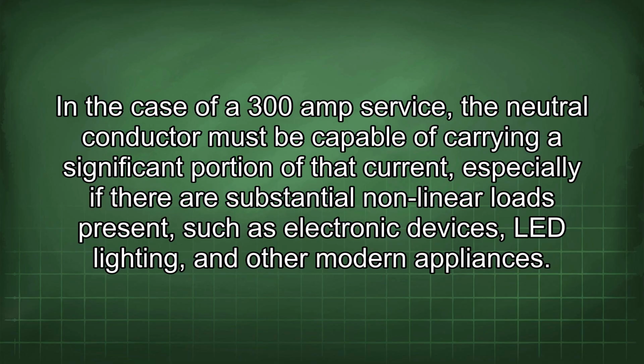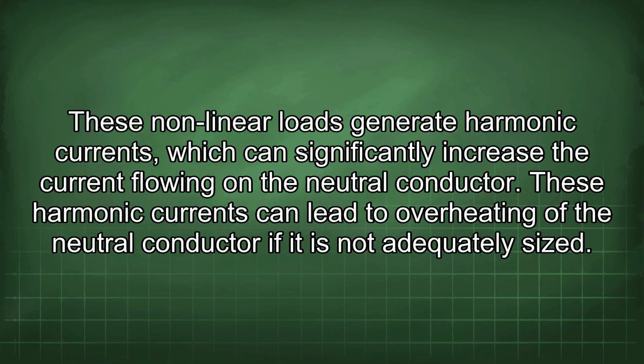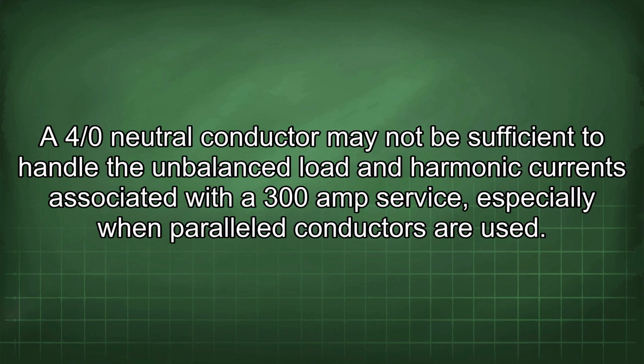In the case of a 300 amp service, the neutral conductor must be capable of carrying a significant portion of that current, especially if there are substantial nonlinear loads present such as electronic devices, LED lighting, and other modern appliances. These nonlinear loads generate harmonic currents, which can significantly increase the current flowing on the neutral conductor. These harmonic currents can lead to overheating of the neutral conductor if it is not adequately sized. A 4/0 neutral conductor may not be sufficient to handle the unbalanced load and harmonic currents associated with a 300 amp service, especially when paralleled conductors are used.